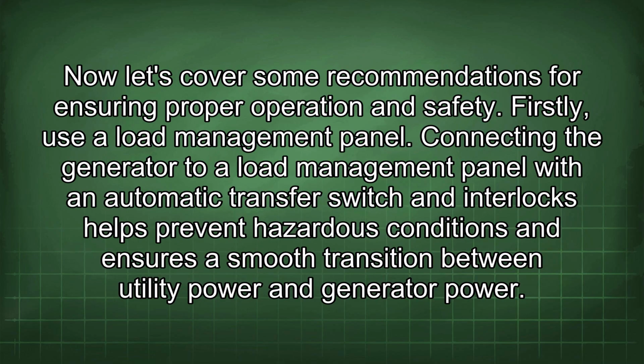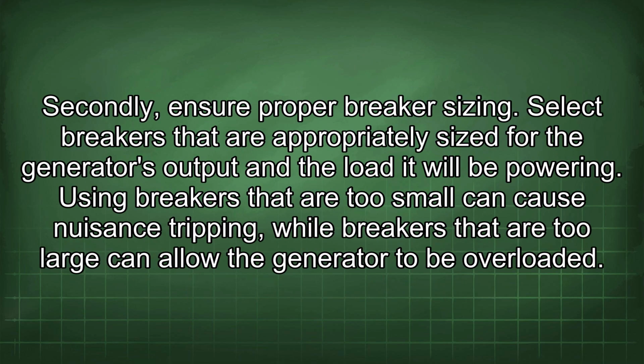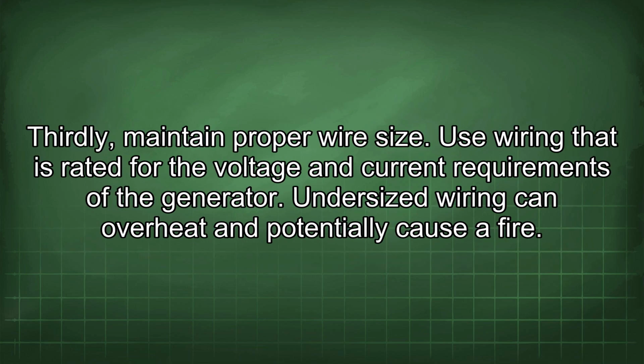Now let's cover some recommendations for ensuring proper operation and safety. Firstly, use a load management panel. Connecting the generator to a load management panel with an automatic transfer switch and interlocks helps prevent hazardous conditions and ensures a smooth transition between utility power and generator power. Secondly, ensure proper breaker sizing. Select breakers that are appropriately sized for the generator's output and the load it will be powering. Using breakers that are too small can cause nuisance tripping, while breakers that are too large can allow the generator to be overloaded. Thirdly, maintain proper wire size.